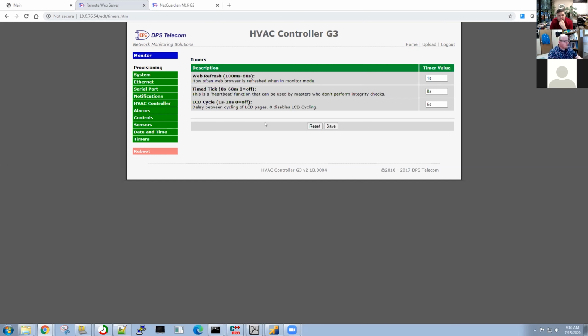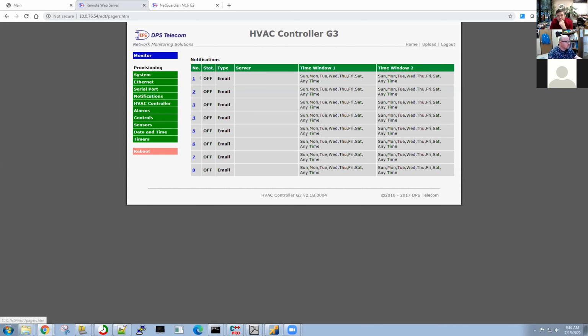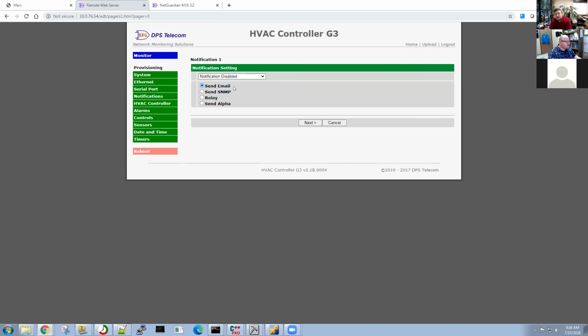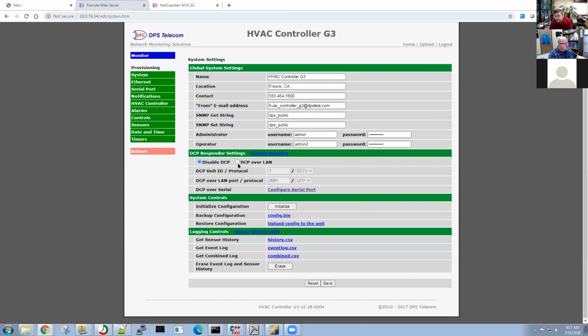Do you have SNMP reporting here? Yeah, I think that's inside of notifications. We can see notifications has the ability to send email, to send SNMP. In certain cases there's spare relays we can trigger to act as a contact closure and notify some physical device on the other end. In this case it's SNMP, but via polling using gets, which I don't think you need to set up to respond to, right? That's just native, whereas this is to set up some traps. If we're setting this up to be an SNMP responder I'll have to review, but I think that's enabled by default. Yeah, we just need to have it switched on.